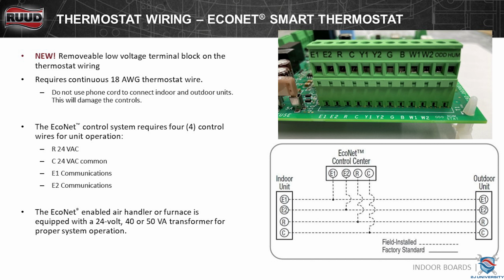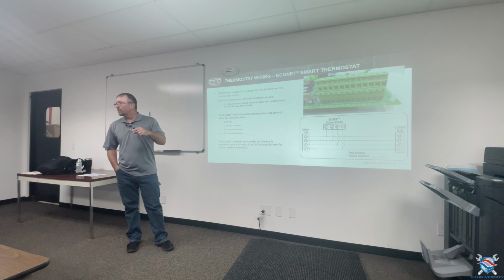Connecting Econet, nothing's changed there. It's still 4-wire. So you're going to have 4-wire in, 4-wire to the indoor, 4-wire to the outdoor. Nothing's changed there. Biggest thing I caution you on Econet, make sure all your E1s are E1s and all your E2s are E2s. If you reverse those, you will get communication errors.